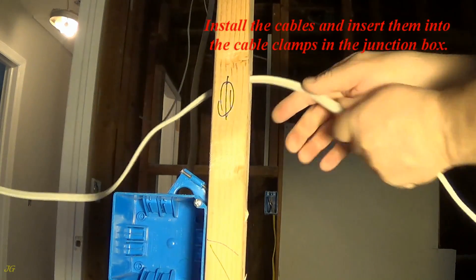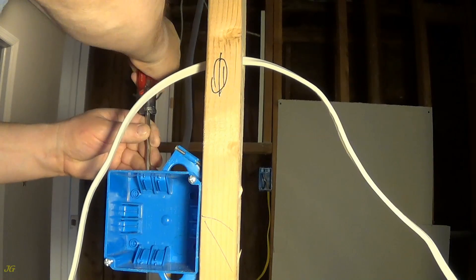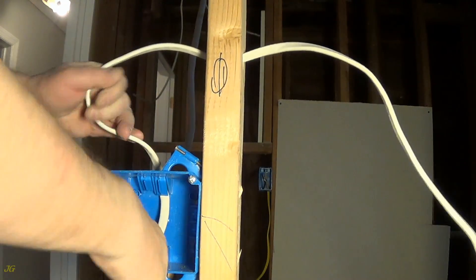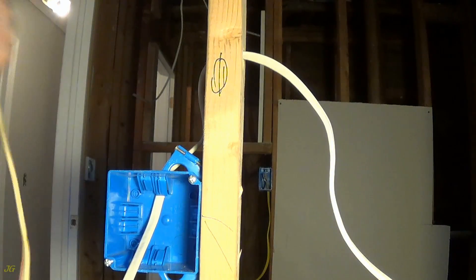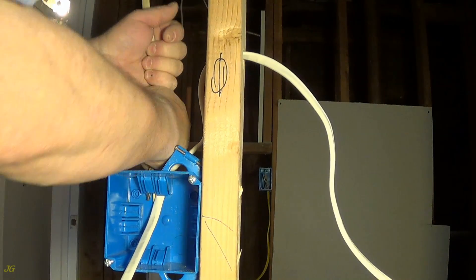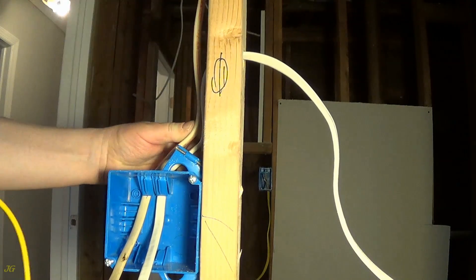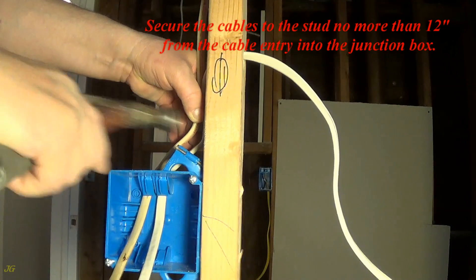Install the cables and insert them into the cable clamps in the junction box. Secure the cables to the stud no more than 12 inches from the cable entry. Install the cable entry into the junction box.